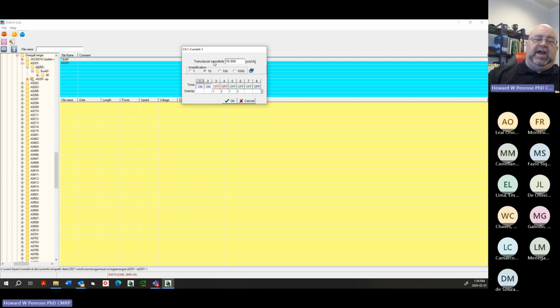Always leave it on 200 amps, which is first off 10 millivolts per amp. If you go to the lower setting, most of them that have that switch pass everything through a little circuit and end up filtering out some of your data. So always leave it at 200, no matter how low you're going.